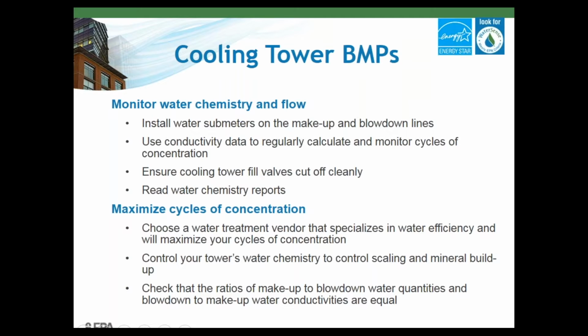As we said, pay regular attention to the conductivity of the water in your tower and calculate your cycles of concentration. If you are not getting the high enough cycles as expected, or low enough, it may mean your control system is not working properly, or there's an unintentional loss of water from the tower. Sometimes this is a result of the fill valve not shutting off properly, so that's another thing it's good to keep a maintenance eye on.